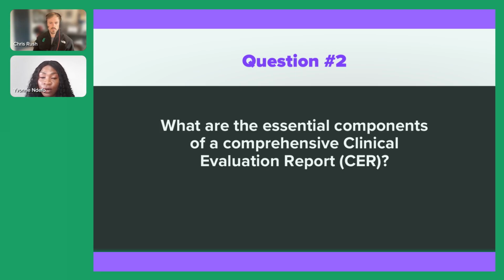And then you have to talk about the intended purpose of your device as well. In that section, you have to talk about what the device does. I know that some manufacturers struggle with phrasing a perfect intended purpose statement. Your notified body takes this very seriously, because the intended purpose of your device determines the risk of your device and the class of your device. You don't want to have an ambiguous intended purpose statement. You want a very direct, very concise statement. However, it should cover everything that your device is doing. And note that any claim you make in your intended purpose statement must be supported by clinical evidence. That's why the intended purpose statement is very important.